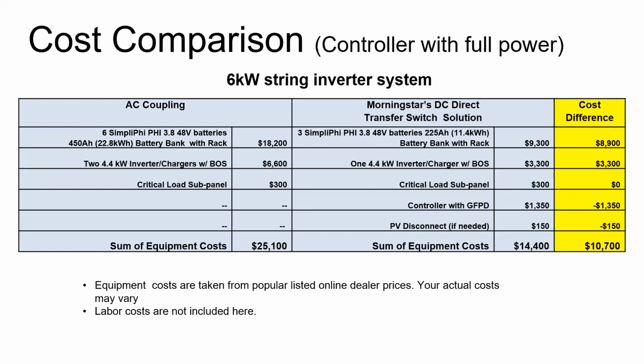Per SimpliPhi's guidelines, we actually require double the output. So if you have 4,000 watts of output, or in this case 8,000 watts of output out of your multi-mode inverter charger, you would need 16 kilowatt hours of battery. So regardless of what the customer originally asked for — 6.6 kilowatt hours — due to the array size in this case, we had to add 2 battery-based inverters, and to match that output per SimpliPhi guidelines, we needed 6 batteries.